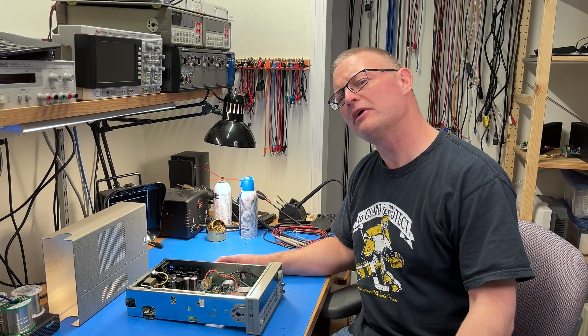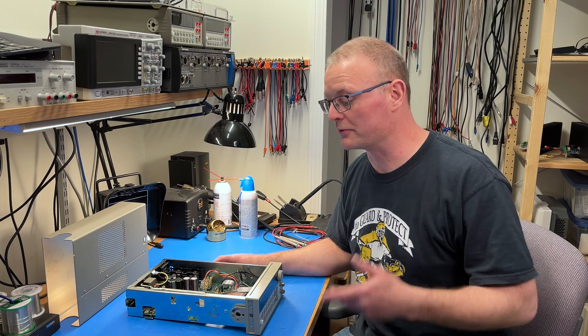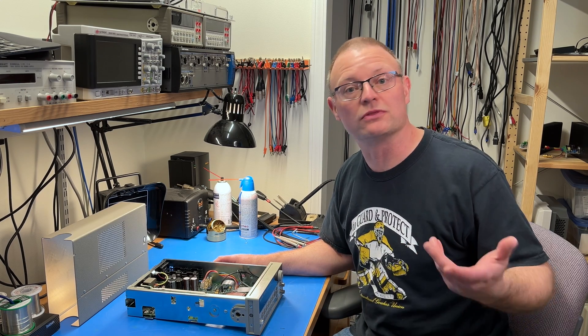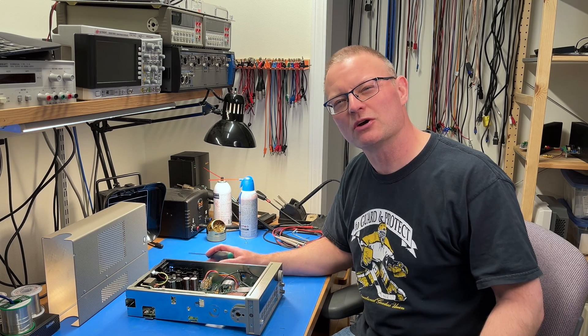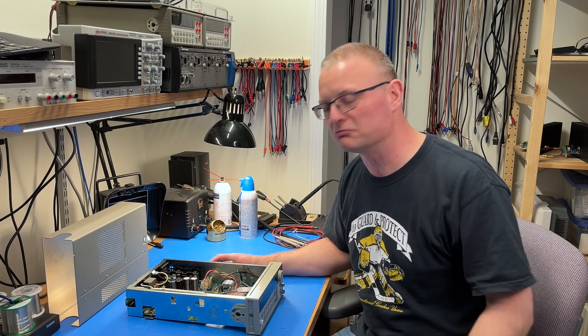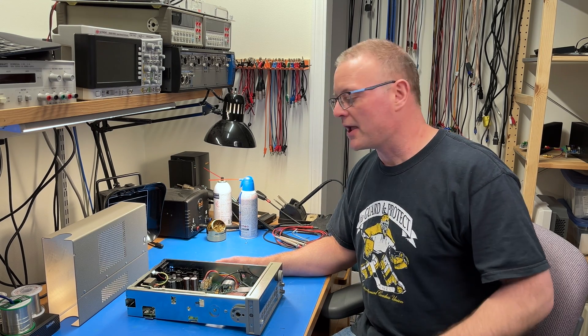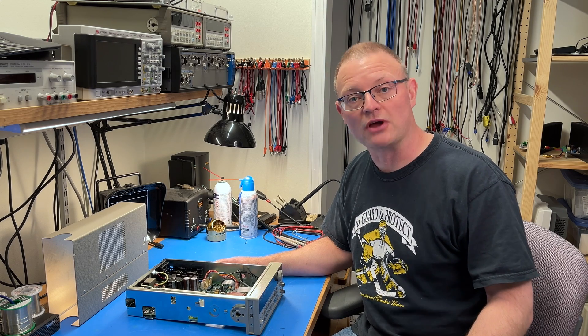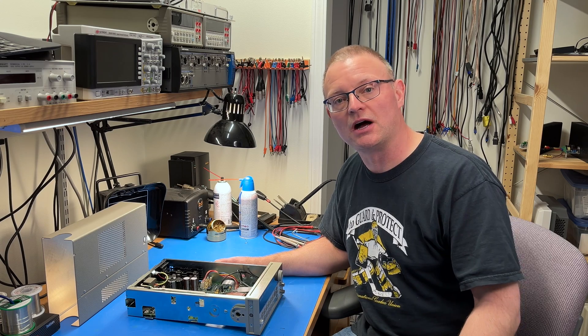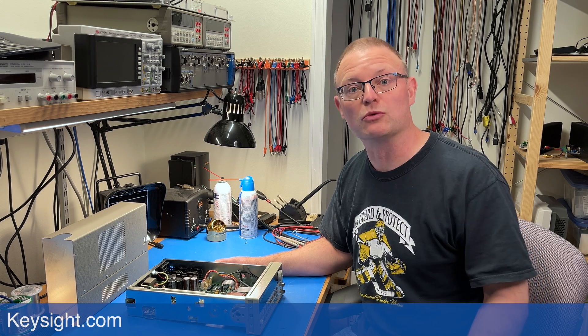I should probably have noted earlier that when you break the cal voids and you open the function generator, you void the calibration. But I'm not touching anything that would require calibration, so I'm not overly worried about that, and of course the warranty is long expired on this thing. It is really handy to have a service manual for this, and I suggest you go to Keysight's website and download it — it's a free download. You might have to give them your email address, but that's about it.